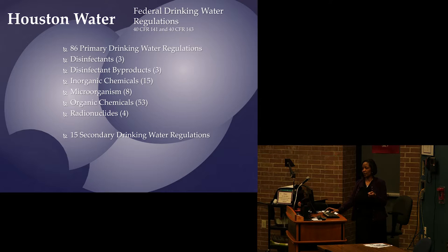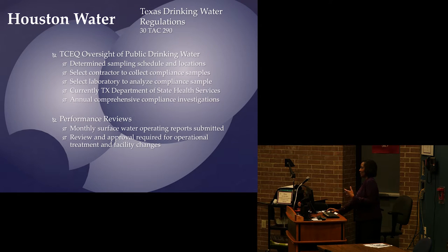The Safe Drinking Water Act has primary and secondary water quality standards. Primary standards cover disinfection — where we add chlorine and ammonia — as well as disinfection byproducts, inorganic chemicals, microorganisms, organic chemicals, and radionuclides. The level of disinfectant we add must be controlled because it can react with organics already in the water and create hazardous byproducts. Secondary standards cover things like taste, color, and odor — there are standards, but we don't receive violations based on whether you like how your water smells.